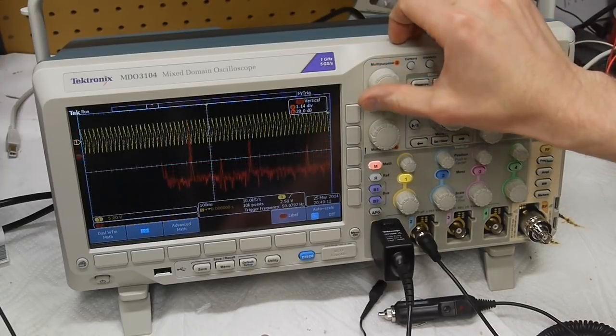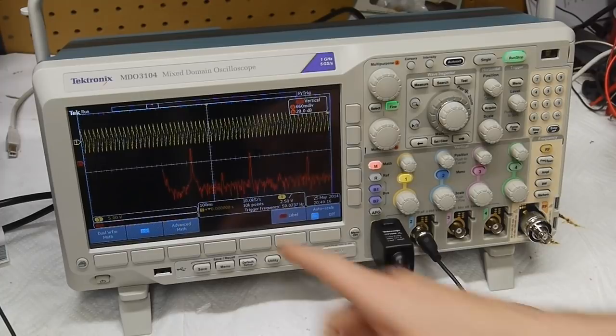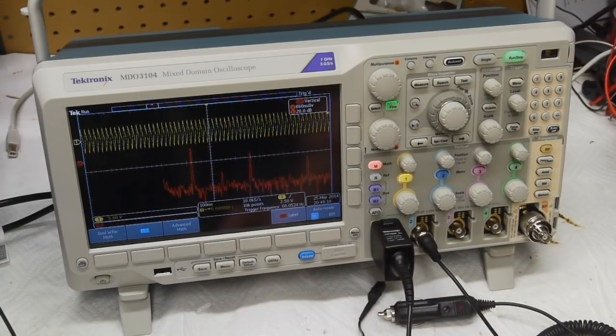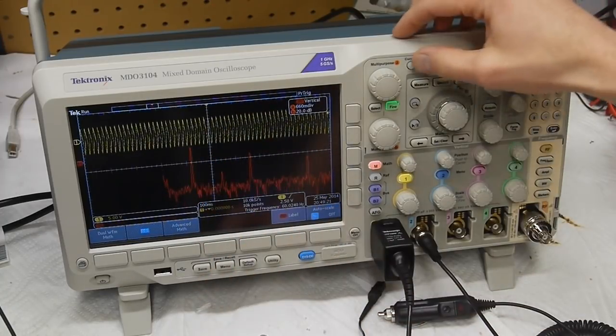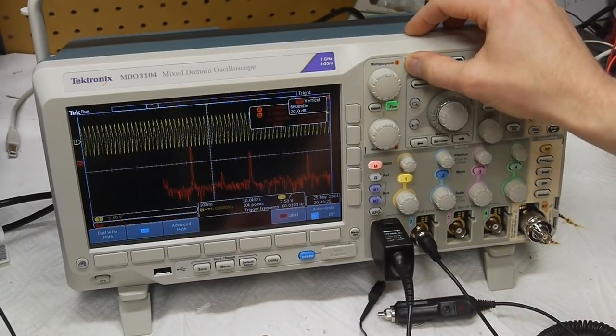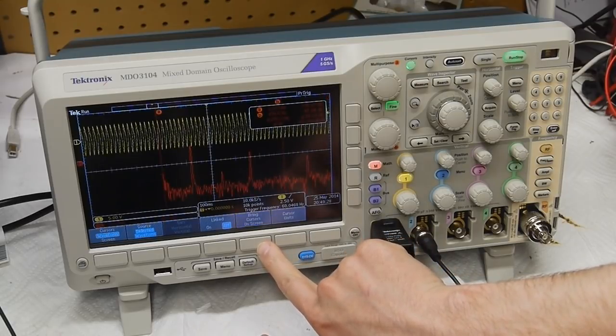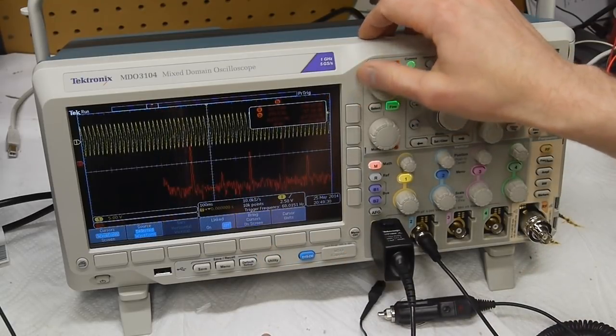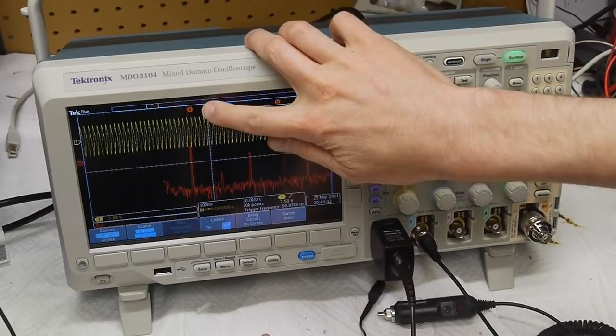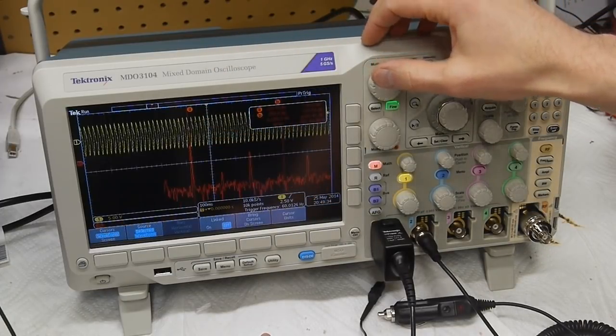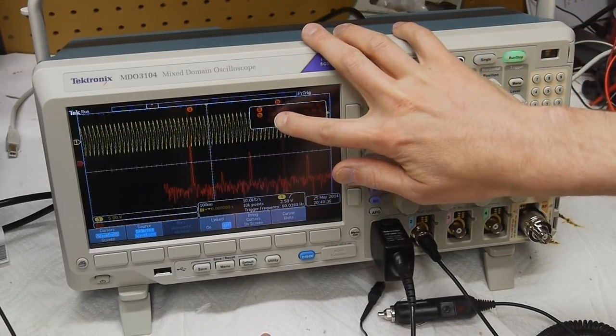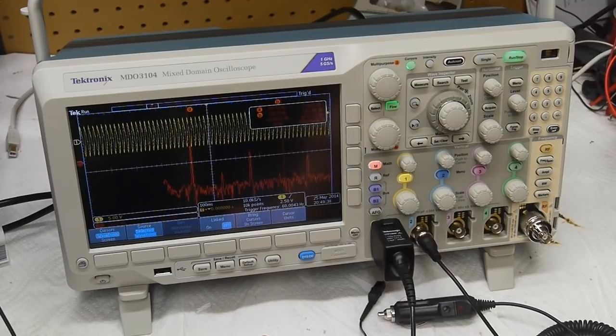So I'm going to move this down just to make it a little easier to see. And we can see we've got a nice peak here. So we could measure this with a cursor. We could turn on Cursors. And if I hold down the Cursors button, it gives me the menu here. So I'll say bring on screen and then use this guy. And it's telling us the A cursor is right about here and the A cursor is 60.5 hertz. So that all makes sense.